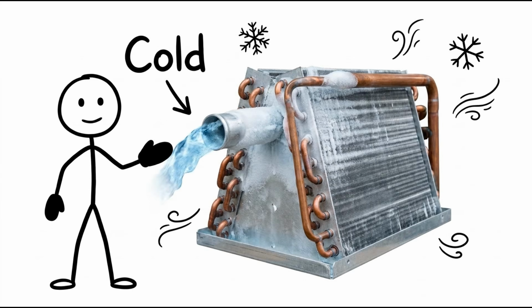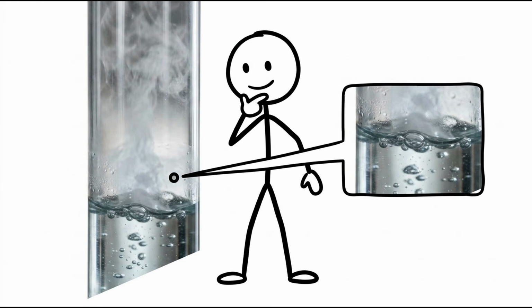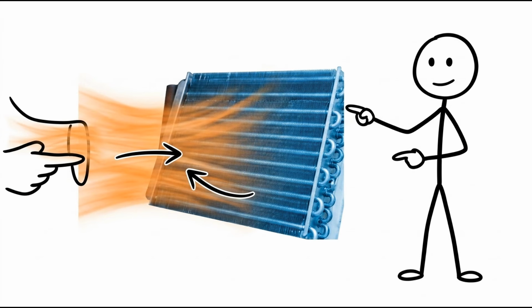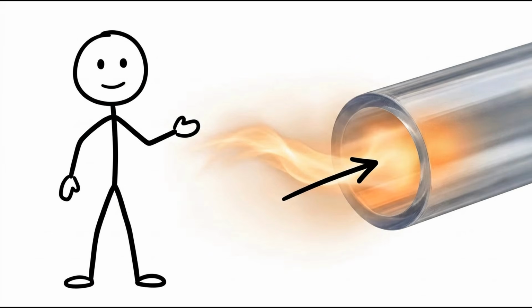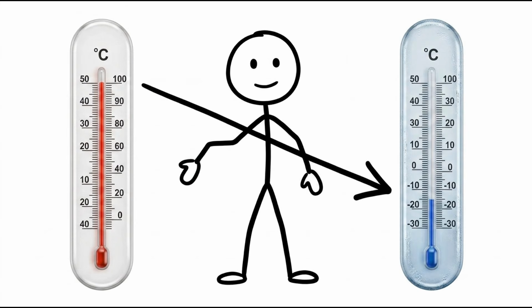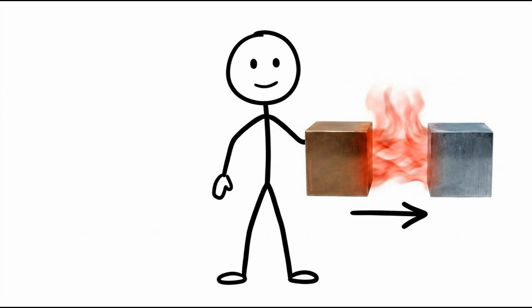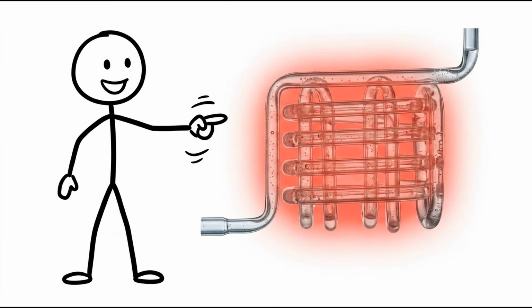When the refrigerant enters the evaporator coil, it is extremely cold and exists as a low-pressure liquid mixed with a small amount of vapor. Because the refrigerant is much colder than the warm indoor air flowing across the coil, heat naturally moves from the warmer air into the colder refrigerant. Heat always travels from a higher temperature toward a lower temperature, and this basic law of physics drives the entire air conditioning cycle. As the refrigerant absorbs heat from the indoor air, something remarkable happens.